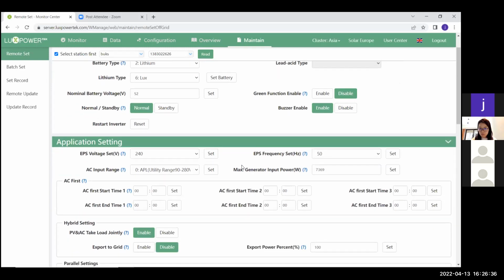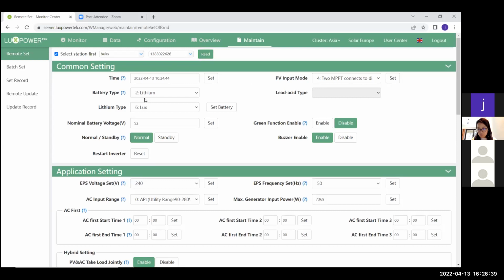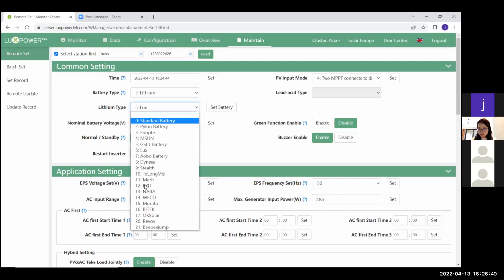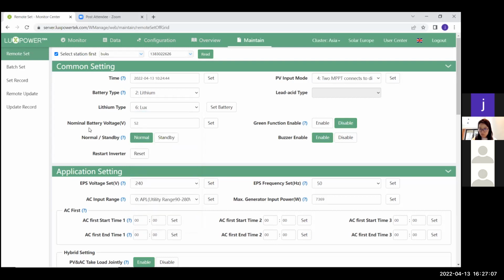From here on, you'll be able to set what type of battery you're using. This system is using a lithium battery. He's using Shoto batteries that are set to the Luxpower protocol, so that's why it's set that way. Here you have a lot of batteries to choose from: your Pylontech batteries, your GSL batteries, Luxpower is usually Shoto, your Dyness, BYDs. All the batteries that we support are in this list. From there, you can type in your nominal battery voltage. For lithium, it's usually 51.2, but a lot of people put it on 52.